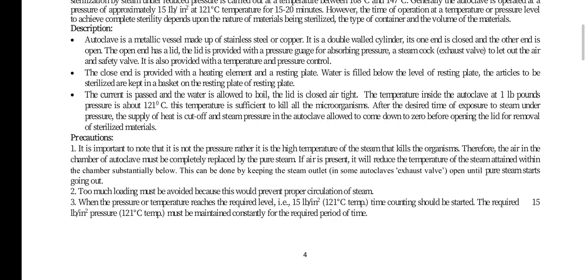Precaution: it is important to note that it is not pressure, rather it is the high temperature of the steam that kills the organisms. Therefore, the air in the chamber of the autoclave must be completely replaced by pure steam. If air is present, it will reduce the temperature of the steam attained within the chamber substantially. This can be done by keeping the steam outlet open until pure steam starts going out.